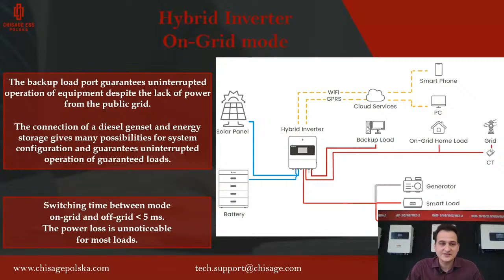So that's easy. When the grid is off, the inverter will switch from on-grid to off-grid in less than 5 milliseconds. So basically, nobody will notice, no light will blink. That's very fast.